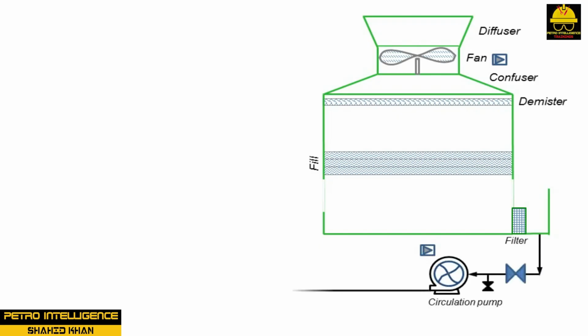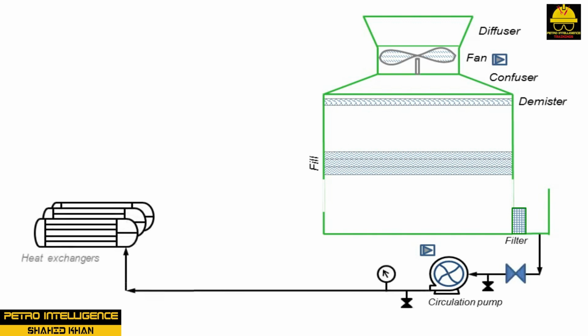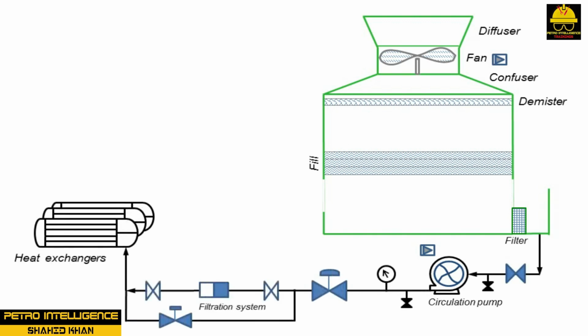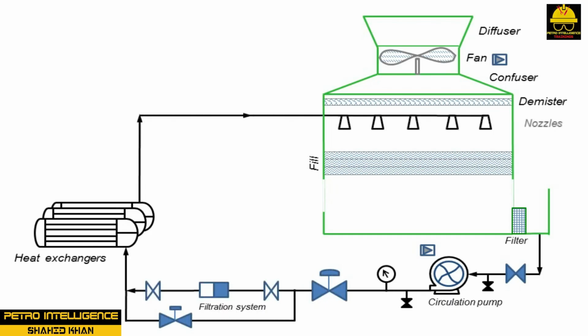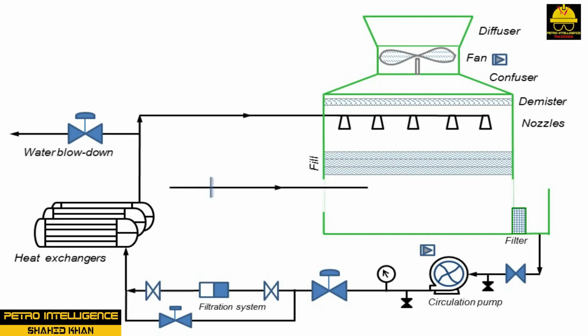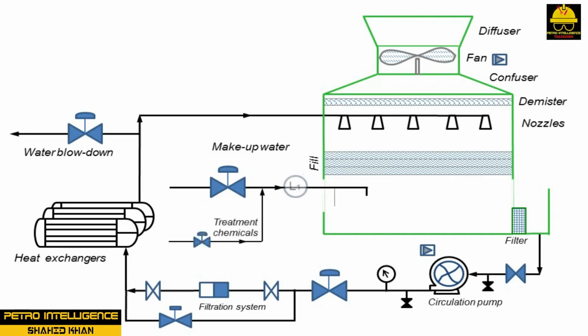The cooling water system is designed for a supply temperature of 90 degrees Fahrenheit or 32.2 degrees Celsius and a maximum return temperature of 120 degrees Fahrenheit or 48.88 degrees Celsius. A cascade arrangement is used to minimize the amount of circulation water while maintaining the design temperature rise. This cascade arrangement takes advantage of process users that are cool enough to maintain a temperature rise between 5 degrees Fahrenheit or minus 15 degrees Celsius and 10 degrees Fahrenheit or minus 12.2 degrees Celsius.